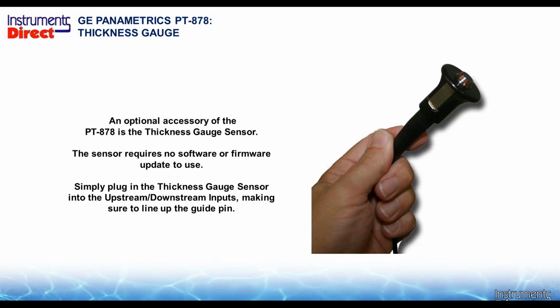If you have ooey gooey on the inside of the pipe, your goop will not be measured by the thickness gauge. If you have 5 years of calcium buildup on the inside of the pipe, it will not see the calcium buildup. It's monitoring, for the most part, the metallic, the rust, and the material, and probably the paint on the outside of the pipe, the thickness gauge.